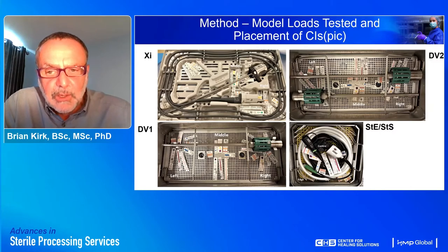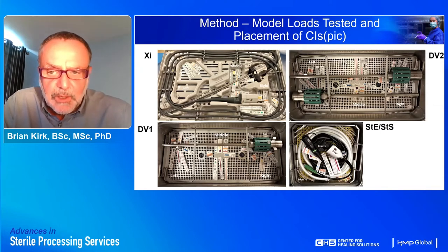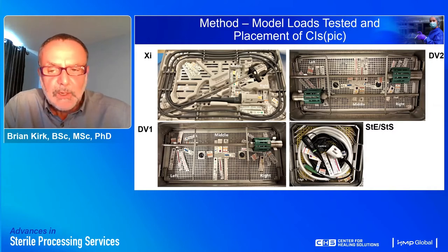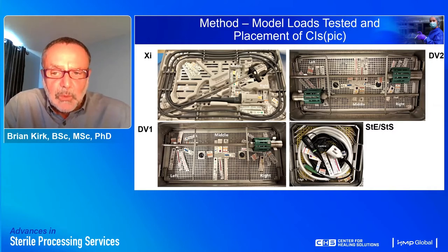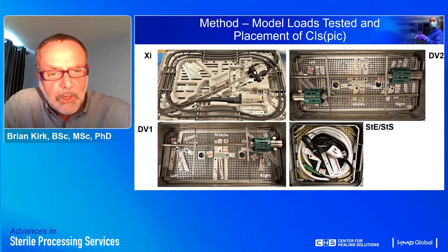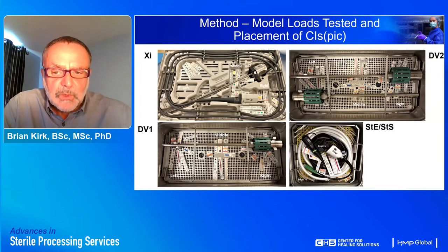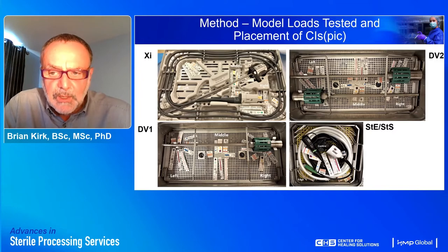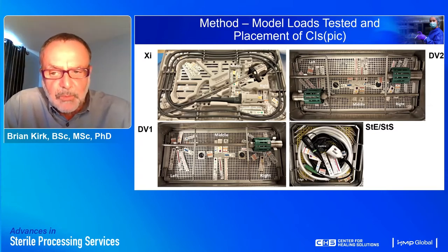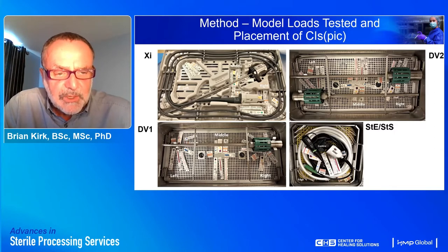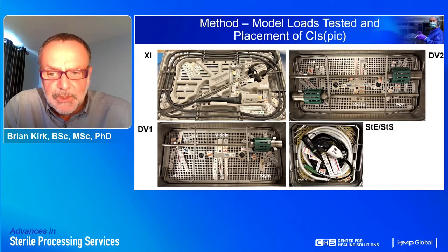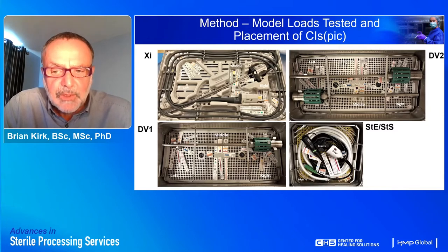In department one, three standard loads were used — XI, DV1, and DV2 — all exposed to an express cycle. The XI was a DaVinci XI endoscope set in its mounting tray, double-wrapped in non-woven sterilization wrap and secured by hydrogen peroxide tape, with a load weight of 7.7 pounds — within the weight limit for that cycle. DV1 was a DaVinci SI probe mounted on pillars in an Aesculap aluminium quad-filter container, weighing about 11.7 pounds, just a little too heavy for that process. DV2 was similar but included two probes, weighing 13.5 pounds.